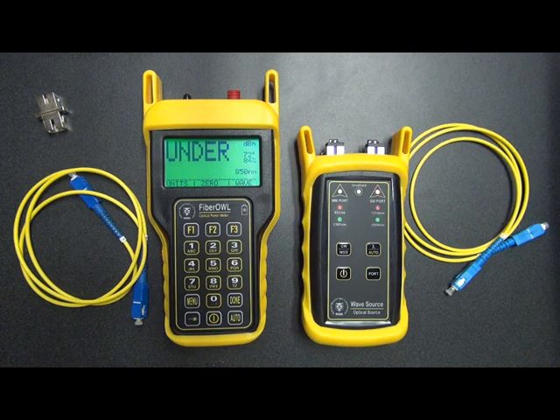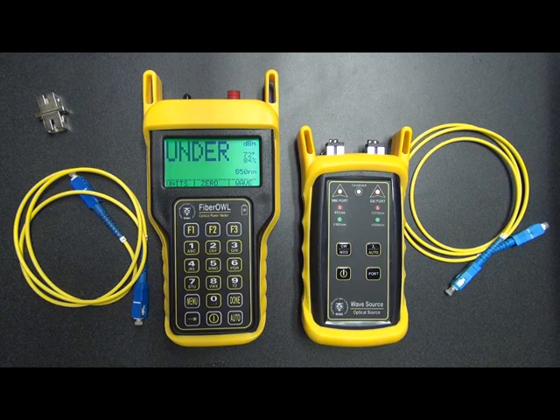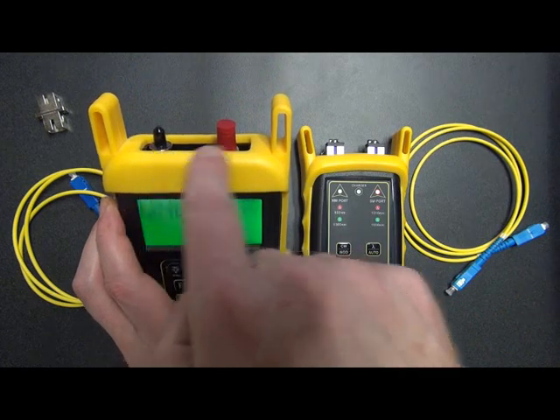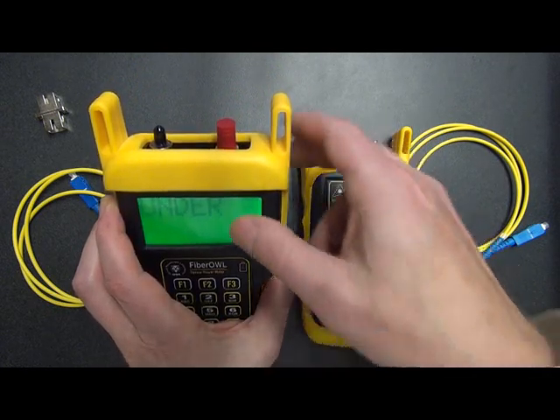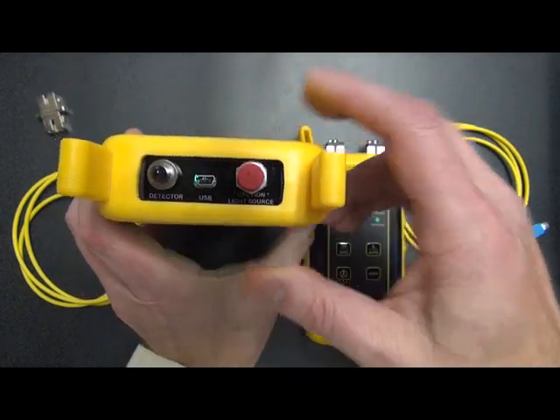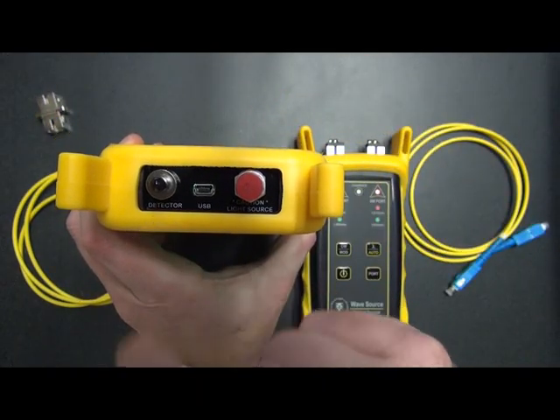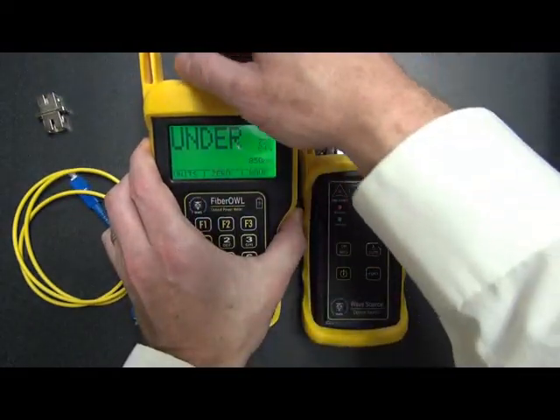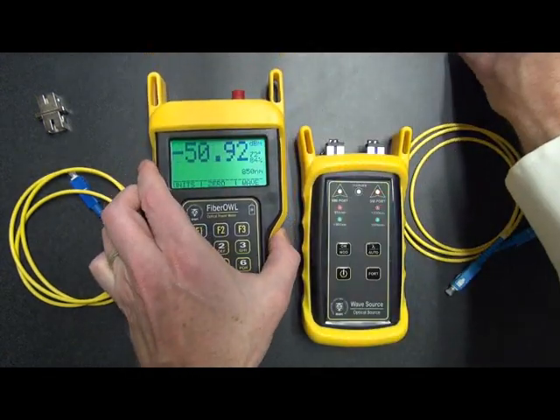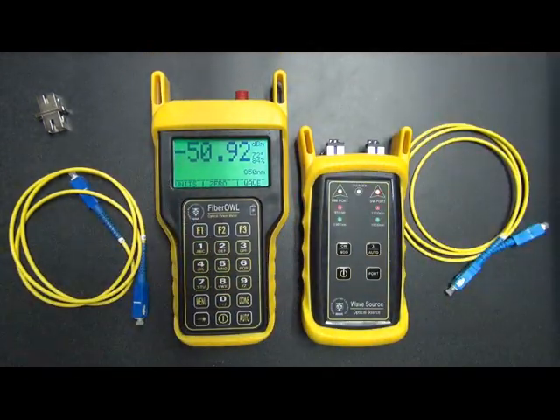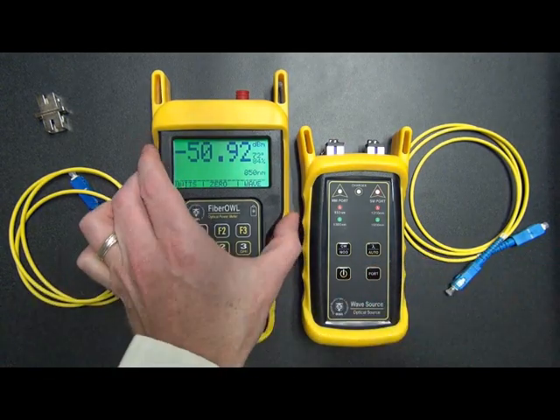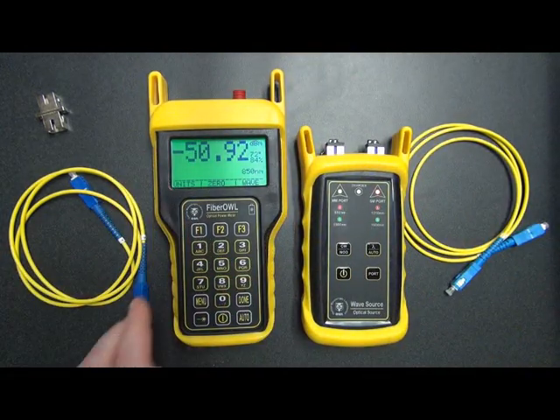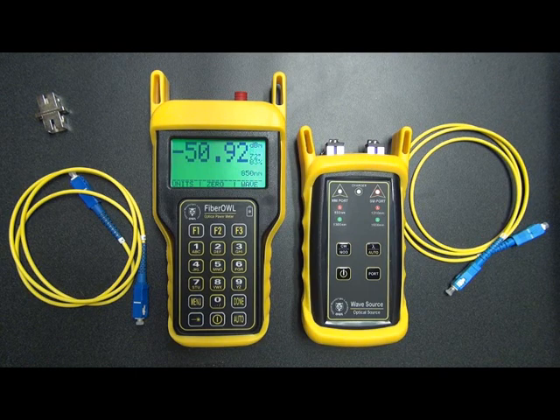On the screen, we'll see the word under. What under means is that there's no light entering the photodetector. You'll notice that there's a dust cap on the photodetector. Fiber Owl power meters will have two ports. You're looking for the port that says detector here. Because there's a dust cap on the detector port, it says under. When we remove the dust cap, you'll notice that we see a power reading. What's happening now is that the power meter is measuring ambient room light. So that's the only light that's coming in here is light from the ceiling. This is normal, so don't worry about that.